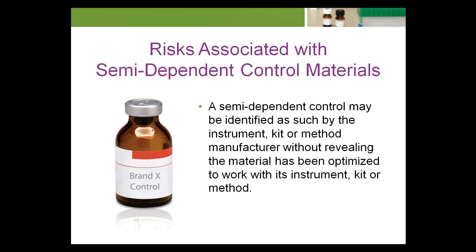On the other side of the coin, a semi-dependent control may be identified as such by the instrument, kit, or method manufacturer without revealing the material has been optimized to work with its instrument, kit, or method. Either situation may lead to risk of harm to the patient if the instrument begins to malfunction, or has malfunctioned and the control does not identify it. Risk of harm increases as the laboratory continues testing, unaware a problem exists with the instrument or kit method.